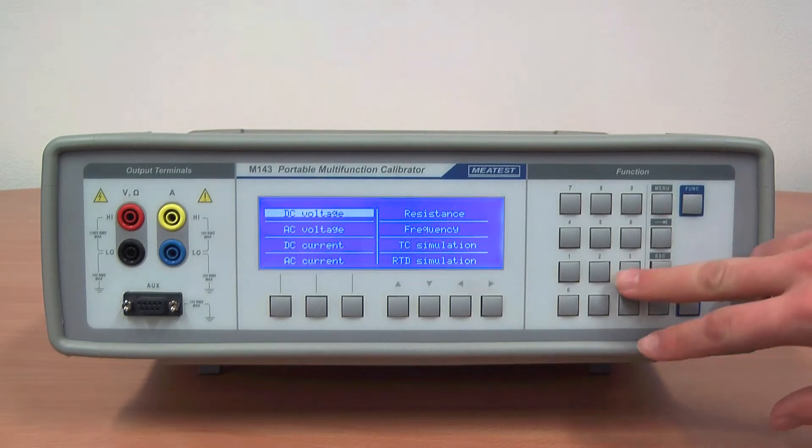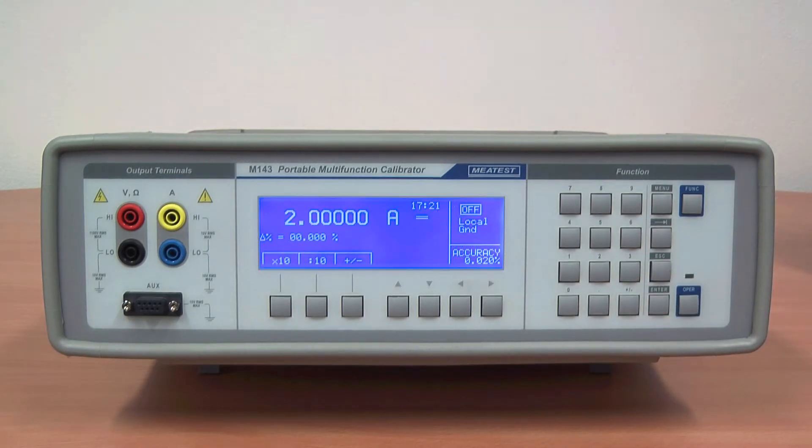Let's start with DC current for instance. In this function you can clearly see the main value, accuracy, output status, allowed deviation and a few soft keys.